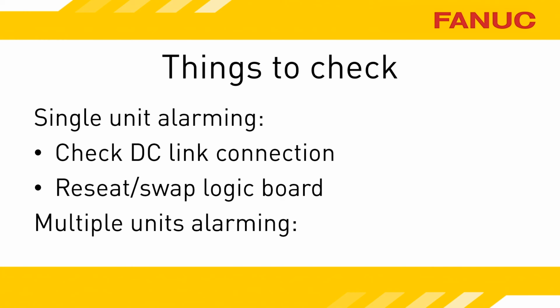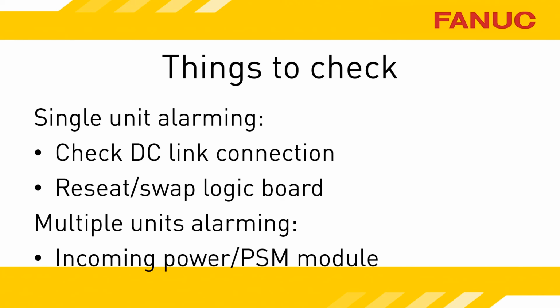If you have more than one unit saying the DC link is low, then take a look at where the DC link is coming from. Check the incoming power. If it's low, get it fixed. If it's fine, your PSM is probably bad.